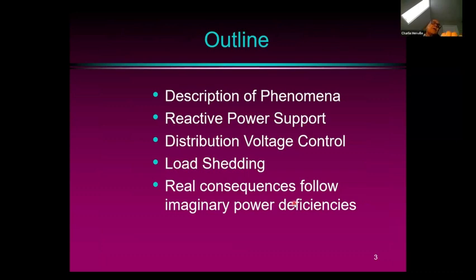So first of all, I'll describe the phenomenon and then talk a bit about how reactive power mitigates the problem. And if the problem still arises, how we can mitigate it further by controlling the voltage at which the power is developed or delivered. And also in the worst case, load shedding. And if those things don't work, then indeed we might have real consequences, which actually would be blackouts.